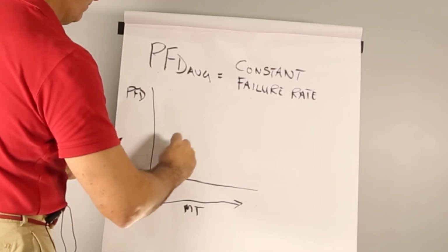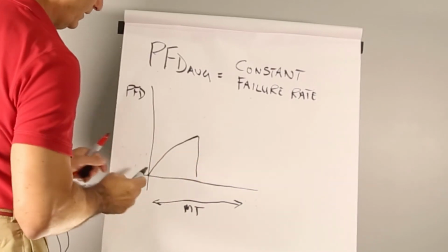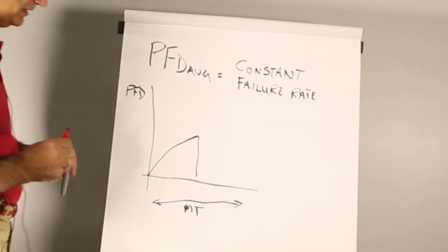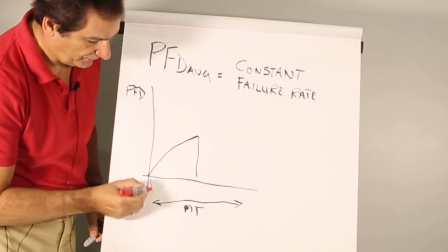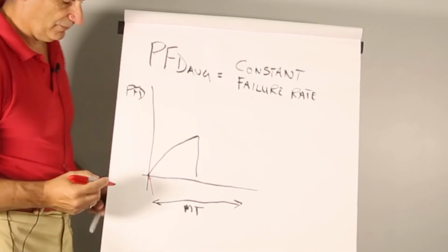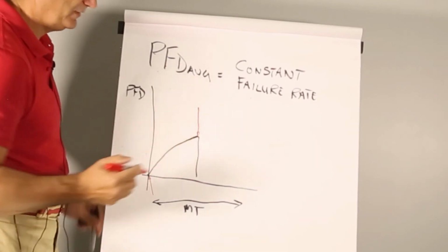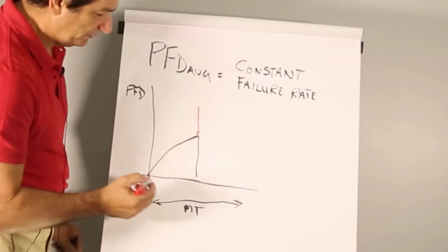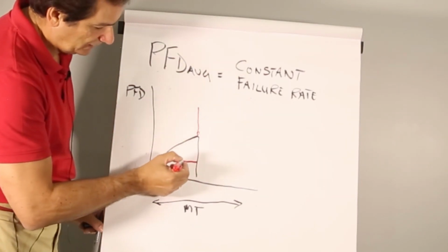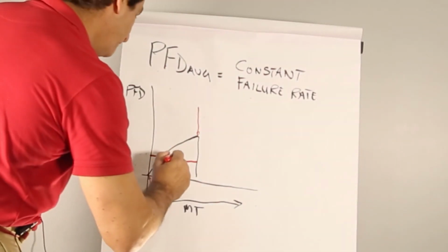We know that during the portion until we do our proof testing, if we get a demand here, we know our PFD average is going to be very low. But if we get a demand here, we know that our PFD average is going to be much higher. So what value do we take? We approximate by taking the mean, the middle, the average.